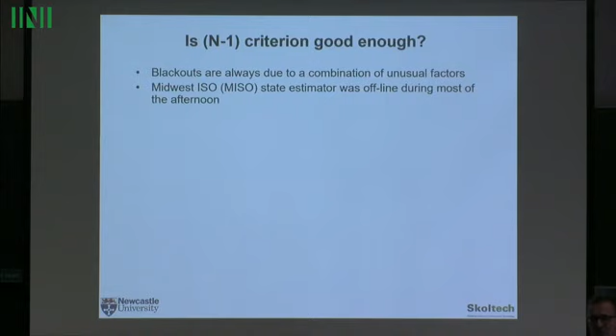So normally the system operators would have spotted it and taken some action. However, the local operator, Midwest ISO, had its state estimator, which assesses the state of the whole network, down for whatever reasons. An alarm and logging system in the local utility, First Energy, failed one hour before the cascade happened. And not only did it fail, but the control room didn't know that it failed. So they were blind, but they did not know they were blind. This is what I mean by a general N-2, which is the computer failure. The line tripped, but the control room didn't know about it, so didn't take any action.